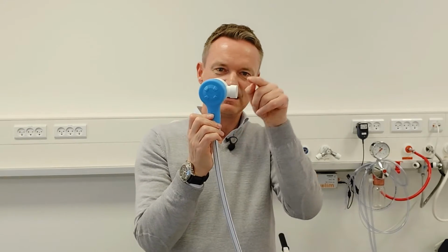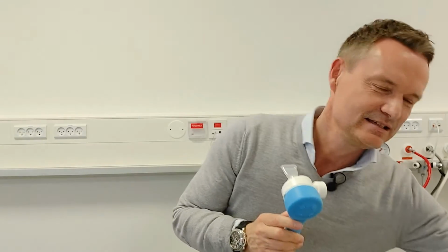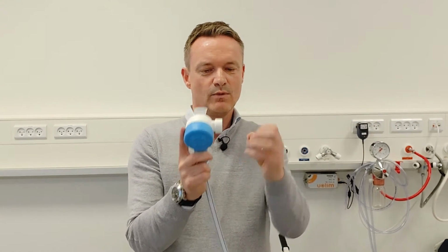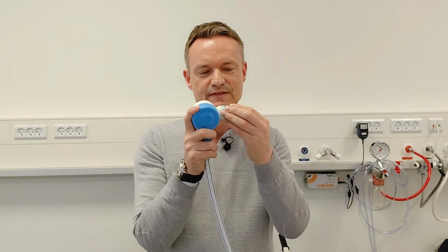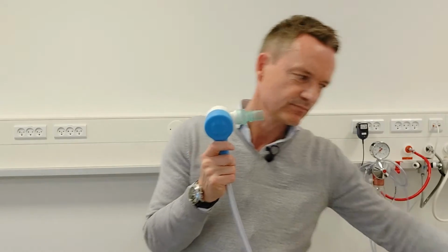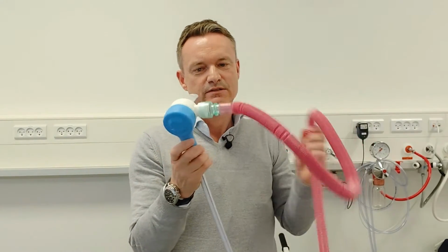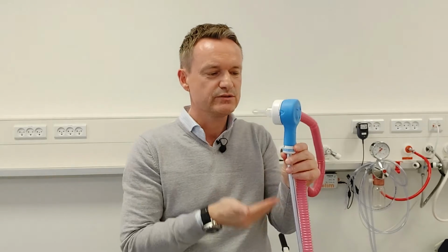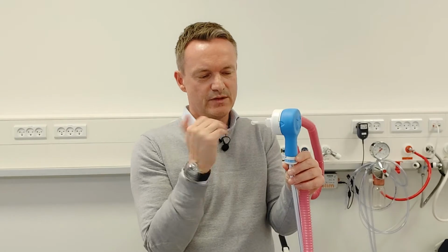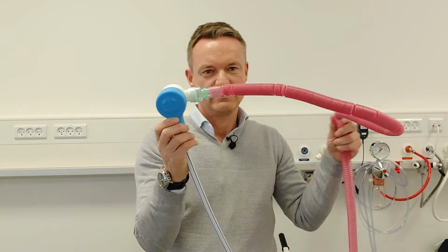I need to make sure that in a closed system I catch this with something and then lead it away. I need to have a connection to that because the diameter of the hose that I'm going to use is smaller and will not fit here. So I add on this connection, meaning that I go from a bigger volume to a smaller volume on the connections. And here's going to be my expiration hose, which I then place onto this one. So now I have the possibility of dosing the gas on a demand valve from a mouthpiece. They will inspire through the mouthpiece. They will also expire into the mouthpiece, and that will then go into this hose.